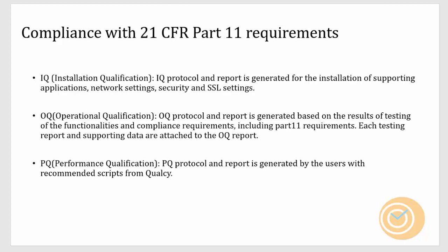After the OQ, you would need to create PQ protocols. Some of the test cases from the OQ, you can use as your PQ protocols. The data migrations and the master data that needs to be part of the systems should be confirmed or qualified, and you can cover that in the PQ protocols.